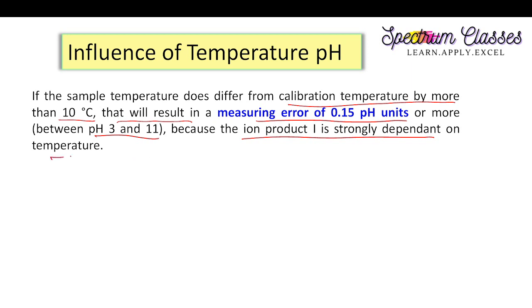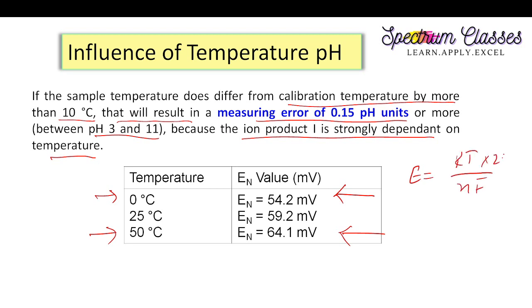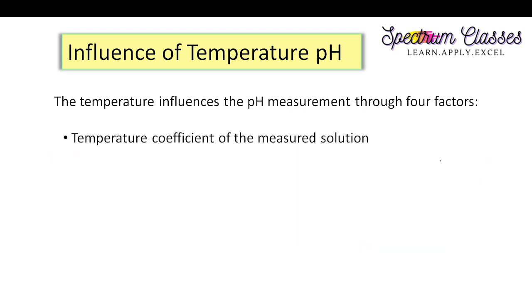You can see from the values: at 0°C the slope factor has one value, and at 50°C it has a different value for the same solution. This is how temperature affects the pH value and the electrode potential. Since E_n = (RT/nF) × 2.303, E_n is directly proportional to temperature — if temperature increases, E_n increases; if temperature decreases, E_n decreases.